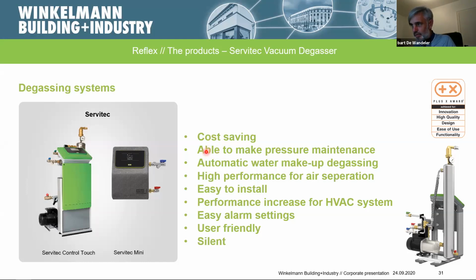We are also able, if we have static vessels, this Servitec can actually maintain the pressure. It can say to a static vessel, hey, your water reserve is not okay, I'm going to give you degassed water so you are sure the system is always full of water. Also at the highest point, so we don't create negative pressure and we don't let air come into the system. So that is, like mentioned here, a high performance air separation, also easy to install. I'll come back to this in the next slide - it's only to show that these systems are not very complex.